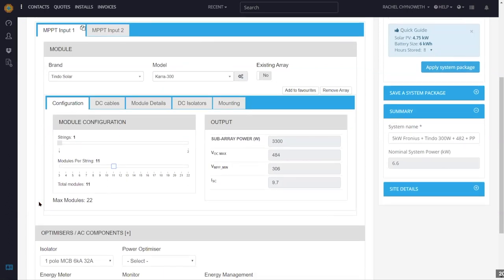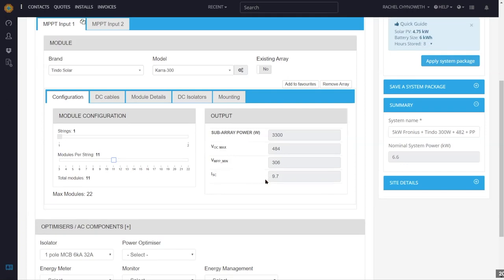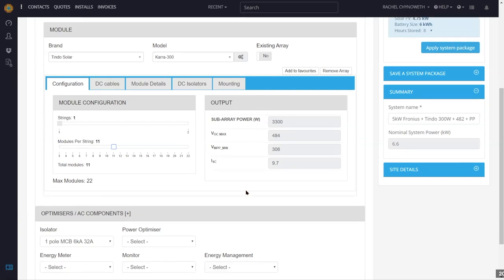Manaz asks: can we add our own inverter and panel data? Not directly — it needs to be entered by us in the background so that information is available when you're designing a system. This includes VOC max, calculated for the lowest temperature at the nearest weather station to the site, and your optimum voltage range. If there is an inverter, panel, battery, energy meter, or monitoring system you'd like to use and can't find in our library, please email the data sheet to our support and we will add it the same day so you can start using it as soon as possible.